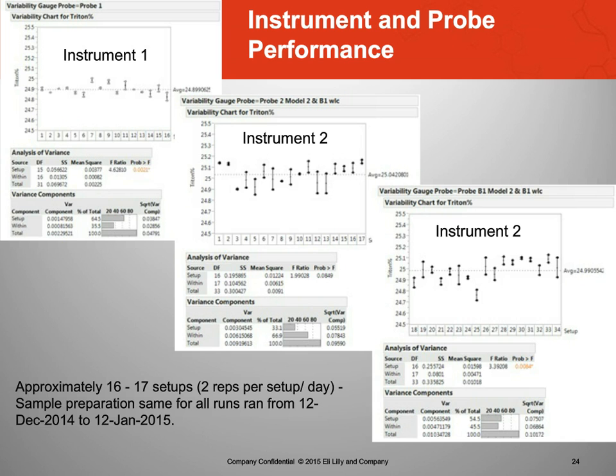If you look at setup and within, most of the variability on probe 1 on instrument 2 is more within run. Basically setup and within run for probe 2 is consistent. But the total intermediate precision between the two instruments is similar, and I think it was around 0.1 for both of them.